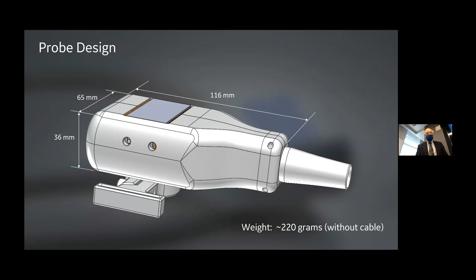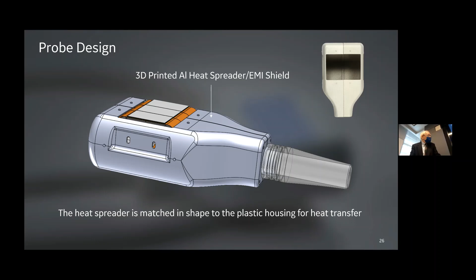Because it is so big, the aperture is so big, it's made up of these 3 individual modules here that we'll talk about in a minute. The ASICs in it dissipate enough heat that we went to the difficulty of putting in an aluminum heat spreader and EMI shield. There are these 3 modules, each of which has 6,000 transducer elements in it. So this is about an 18,000 element transducer array.